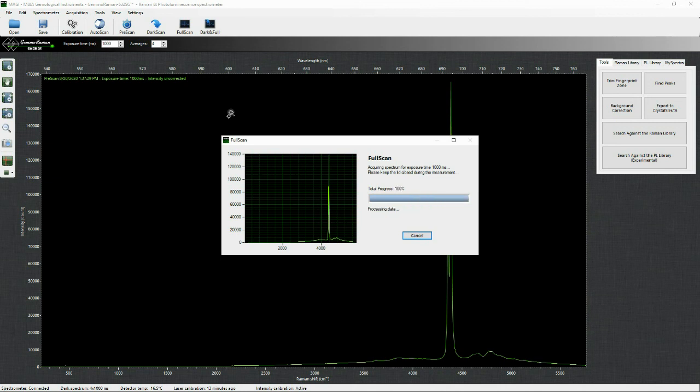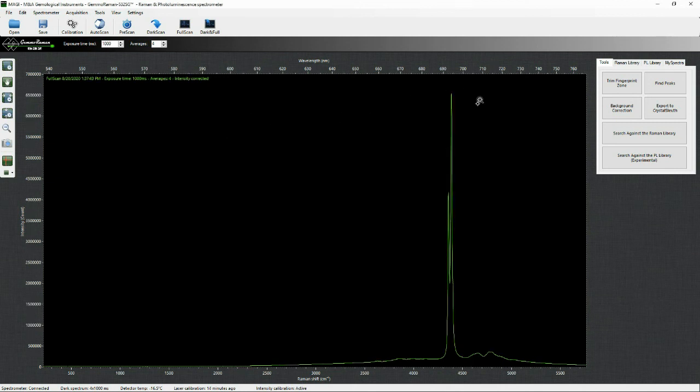It's important to underline that since the laser beam is focused on the surface of the sampling disc, the Raman fingerprint spectrum taken with the neutral density filter cannot be used to identify a stone placed upon it.